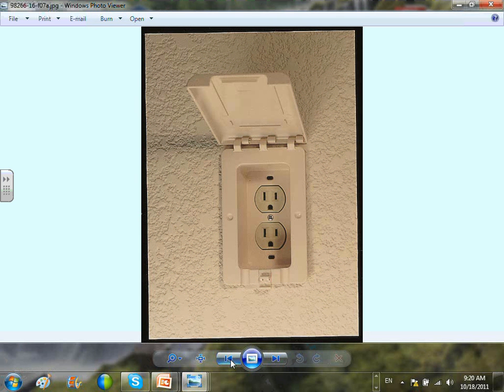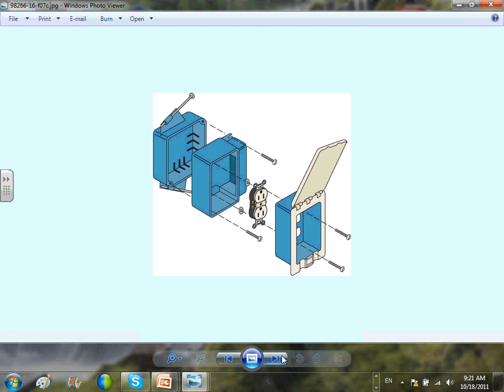Okay, so say your parents' house does not have it. Take this. If you were to go change this receptacle right now, based on 2011, change it, not pulling wire, you have to have a weatherproof, GFCI, tamper resistant receptacle. In-use cover, a lot of inspectors will force you to use an in-use cover also. If you change it. If you don't change it, we're okay. We trust that you're not going to mess with it.